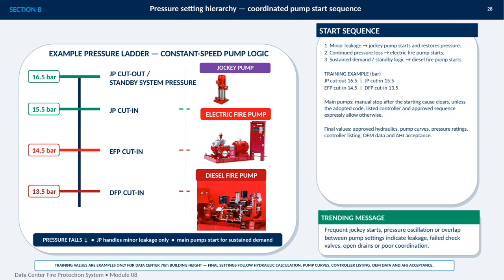At 16.5 bar, it is shown at cutout, and when pressure falls to 15.5 bar, it starts to restore pressure caused by minor leakage. If pressure continues to fall, the electric fire pump starts at 14.5 bar. With sustained demand, or under the applicable standby logic, the diesel fire pump starts at 13.5 bar. This staged response helps distinguish small losses from a genuine firewater demand.